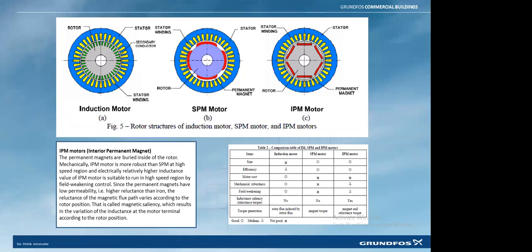In that case, all the permanent magnets are embedded inside the rotor itself. So it gives better mechanical stability, since normally all permanent magnet motors run at a higher speed compared with induction motors. Normally, induction motors have a synchronous speed of 3000 rpm. A permanent magnet motor may go to 4000 rpm or 4500 rpm, depending on the design. That's the reason we have to ensure better mechanical stability, and to ensure it we have the embedded magnet construction in our IE5 motor.